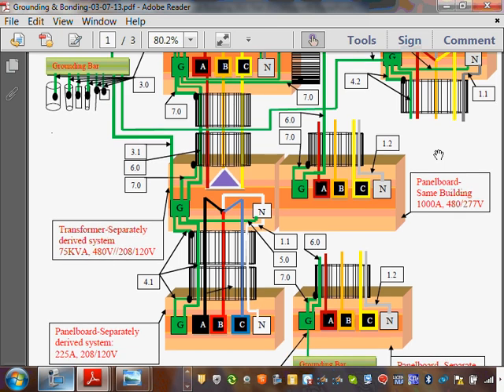Only in the US will you see a system like this. Most of the world uses 220, 230, 240, or 250 to ground. So they run all their lights and receptacles at 220, 230, 240, or 250, all of Europe. Almost 80% of the world is at 220, 230, 240, or 250.